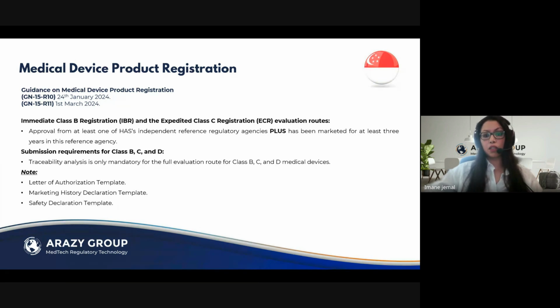The key updates in this revision mainly focus on, first, eligibility criteria within specific evaluation routes, notably for the immediate Class B registration and the expedited Class C registration evaluation route. A device must now not only obtain approval from at least one of the HSA's independent reference regulatory agencies, but also have been marketed for a minimum of 3 years in this reference agency.